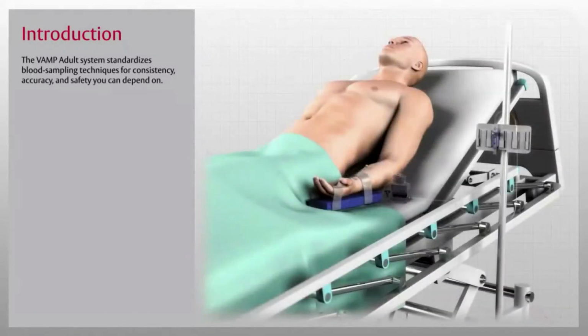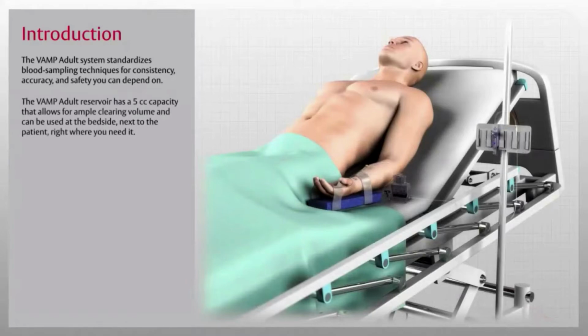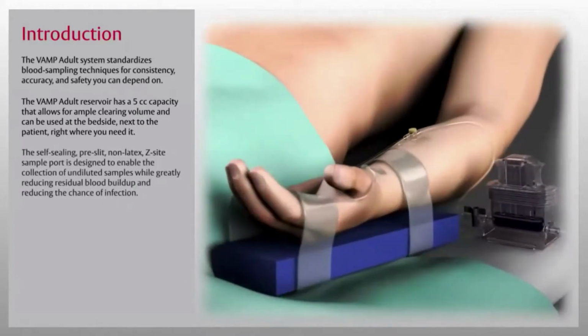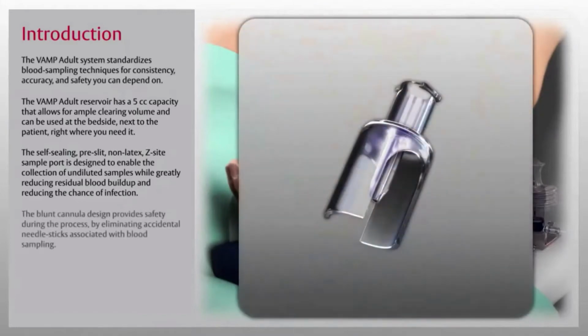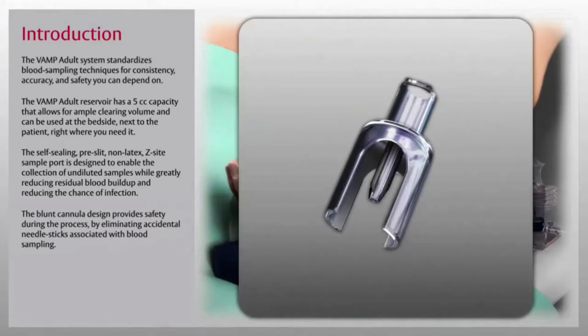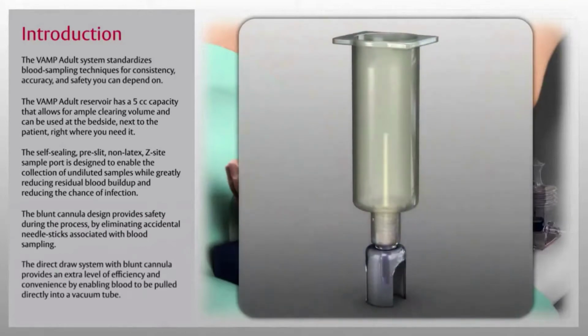Setup, priming, sampling, and flushing are quick and easy with the VAMP Adult System. The VAMP Adult Reservoir has a 5 cc capacity that allows for ample clearing volume and can be used at the bedside, next to the patient, right where you need it. The self-sealing, pre-slit, non-latex Z-Site sample port is designed to enable the collection of undiluted samples while greatly reducing residual blood buildup and reducing the chance of infection. The blunt cannula design provides safety during the process by eliminating accidental needle sticks associated with blood sampling. The direct draw system with blunt cannula provides an extra level of efficiency and convenience by enabling blood to be pulled directly into a vacuum tube.